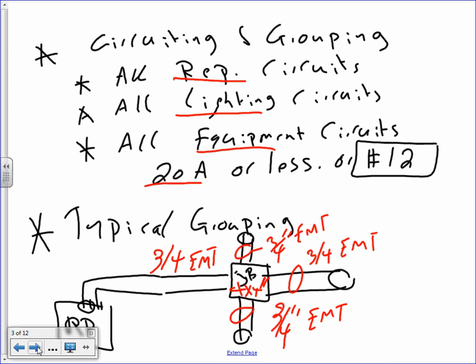Cool? Now this is talk of a contractor, not an engineer. Engineers, we care less. We just throw a circuit and call the electrician to circuit it. Contractor, you need to know how to group them. How are you going to take all these circuits, each one of them 15 amp or 20 amp, out of this panel to everywhere else in the building? That's where grouping becomes a big deal. Okay, can I get you to understand that for all receptacles, all lights, all equipment, 20 amp or less, it's a very good idea to group them as they come out of the conduit. Thumbs up, Chad? We understand that?